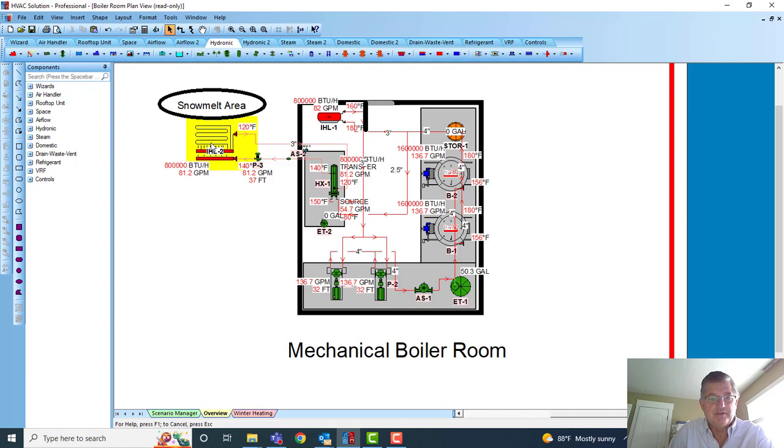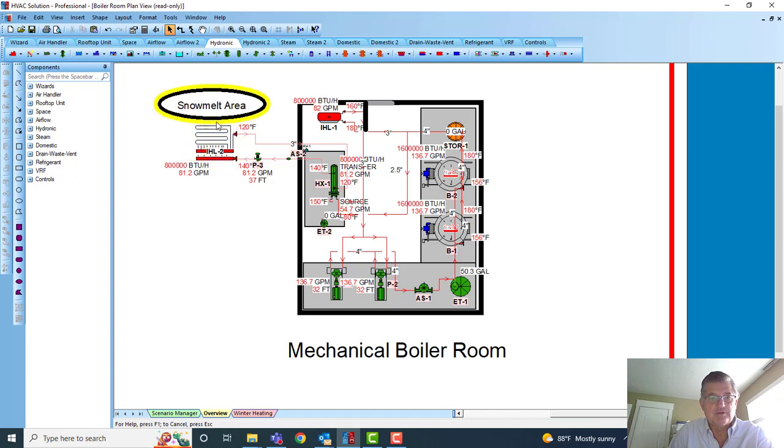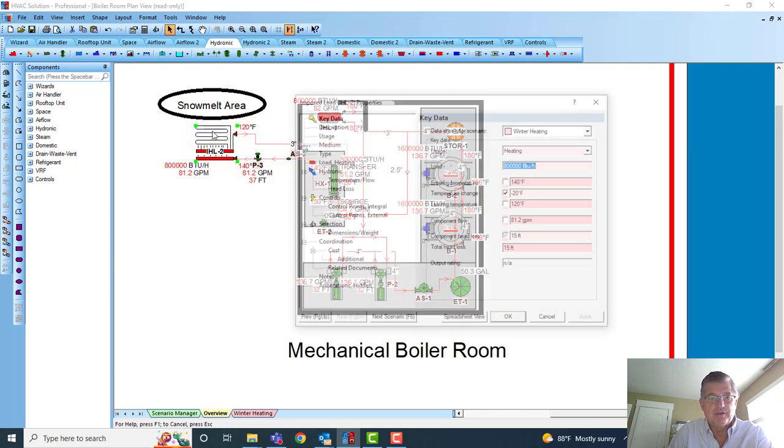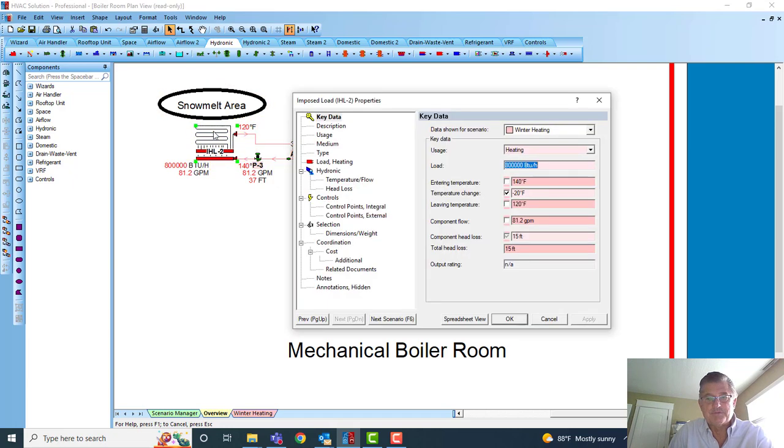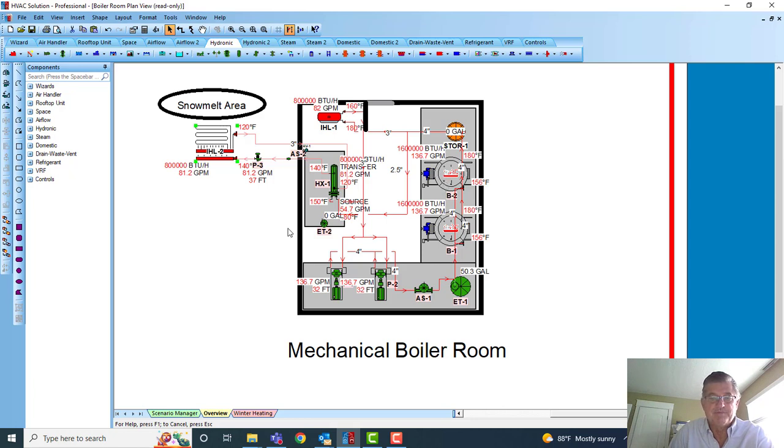Same thing here, you'll see this project's mechanical boiler room—a couple boilers, pumps, expansion tanks. It's serving a unit heater there as well as a snow melt load. There's my load there, so many BTUs. That BTU's with the unit heaters now obviously goes back to the boilers, divided by the delta T of the different loads there, coming up with flow.